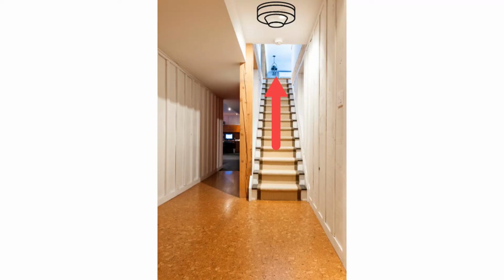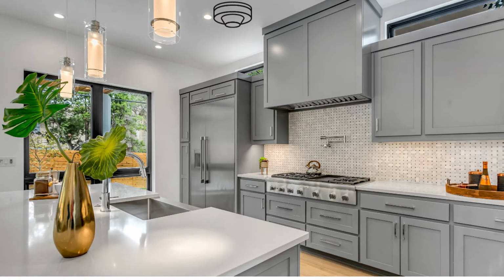Okay, now for the locations. There is to be a smoke alarm on every habitable level, including in basements at the base of each staircase leading to an occupied floor above. The floor above has to have living space in it. If the smoke alarm location is further than 20 feet from the kitchen or full bathroom doorway, you must install a smoke detector in that area.